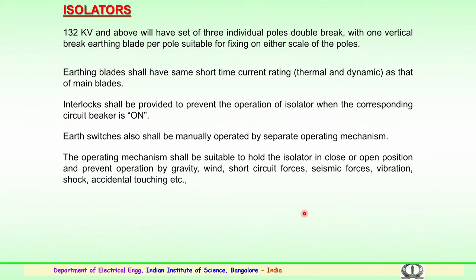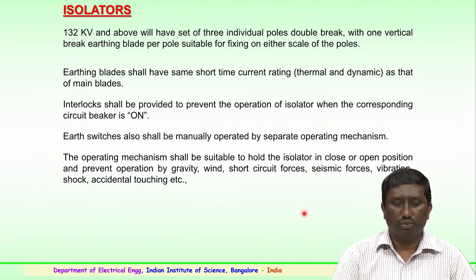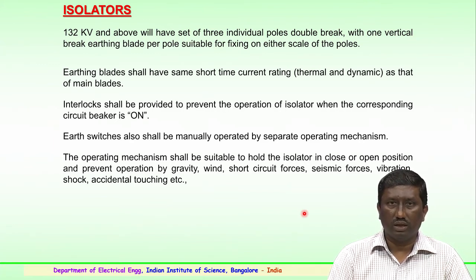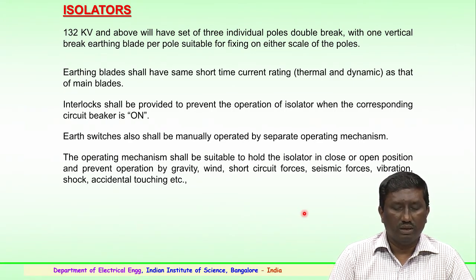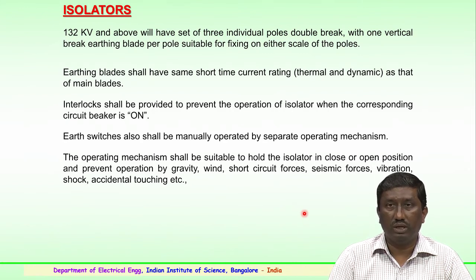The first component is the isolator, which is a very important component in any substation. It mainly helps in the proper maintenance and isolating of the circuit during maintenance. For 132 kV and above, there is a set of three individual poles with a double breaking arrangement and one vertical break earthing blade per pole. These are suitable for fixing on either side of the poles. The isolators have earthing blades and a short-time current rating, both thermal and dynamic, similar to the main blades.